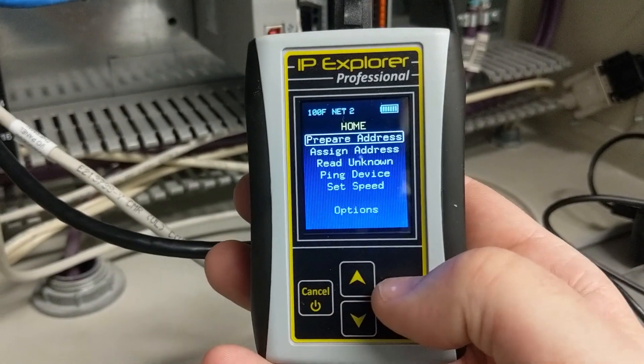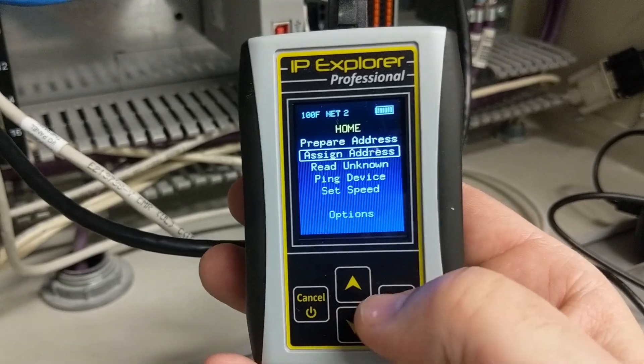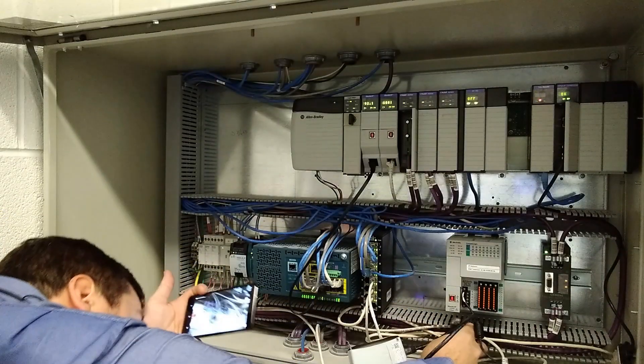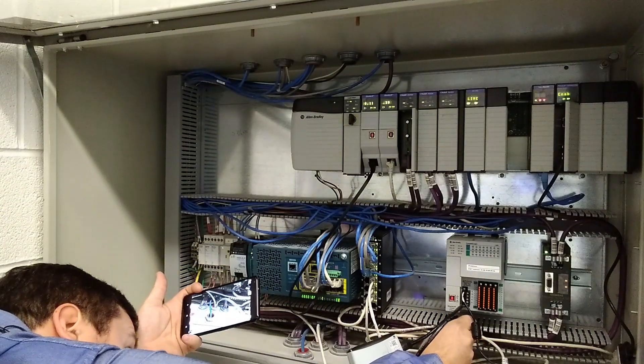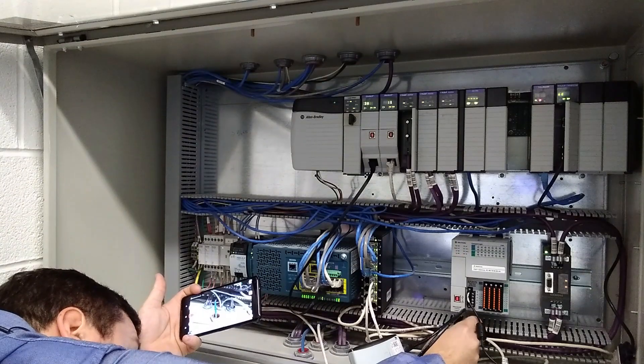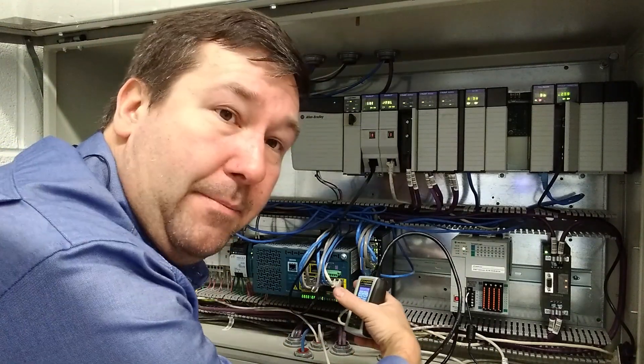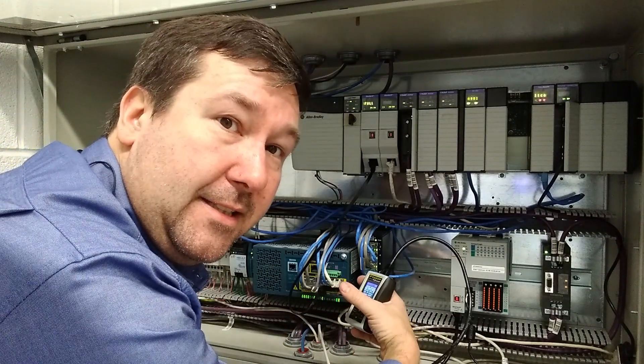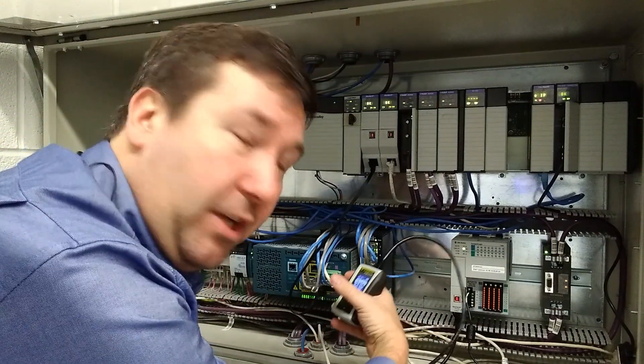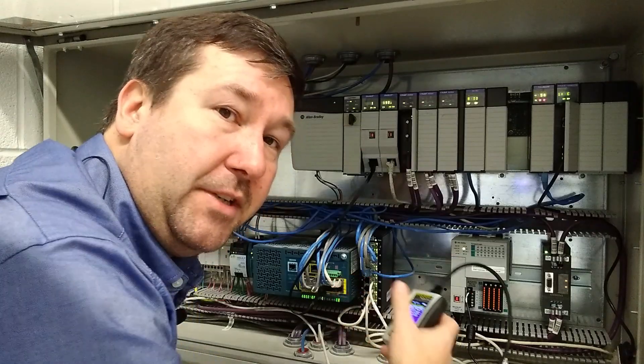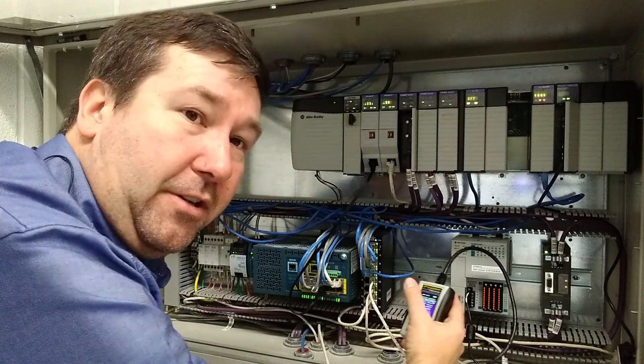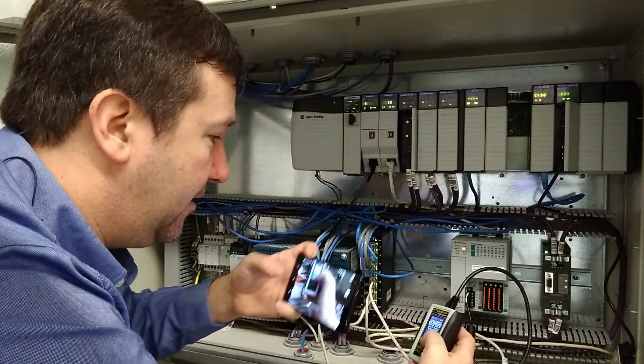So what I'm going to do is cancel out of this, and I'm going to go to assign IP address. And then I'm going to plug it into my CompactLogix. Now while we can read IP addresses easily by plugging into an ethernet switch, when you go to assign an IP address, plug directly into the device.